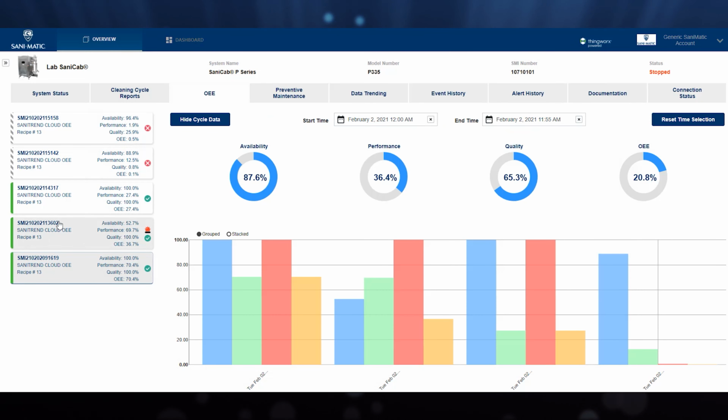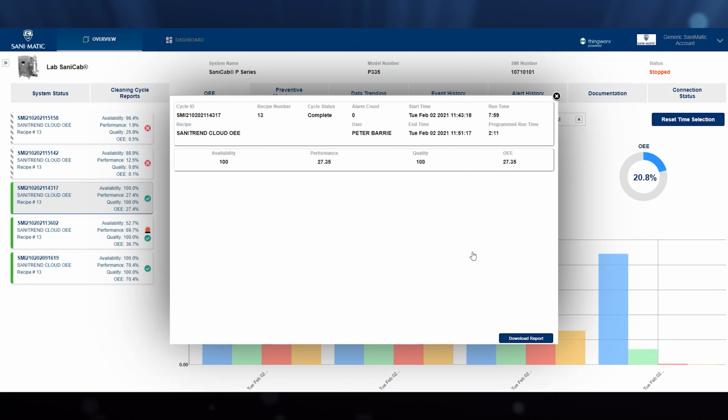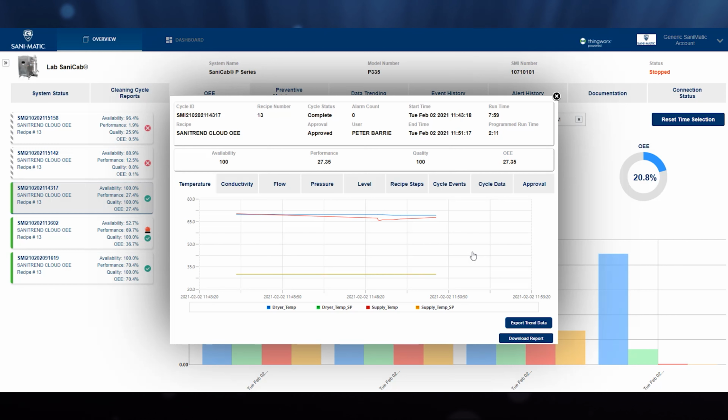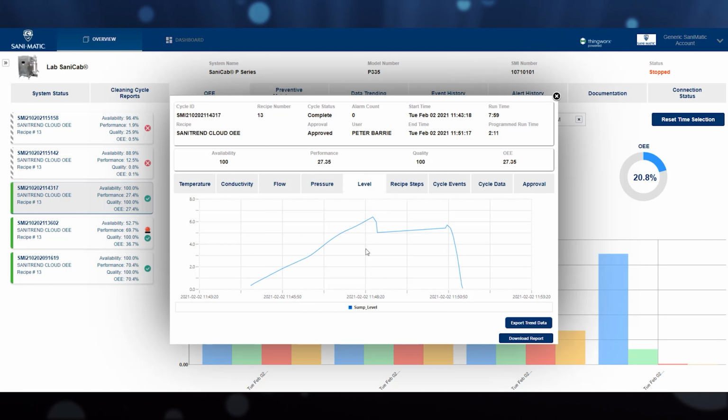And now I'll jump over to our recipe where we closed that water valve a little bit, right? So that water fill took a lot longer to fill up. And I can see that actually if I look at the level, right? Instead of a quick fill that we would have seen in our perfect recipe, I filled over 2, 3, 4 minutes or so. And this is common, right? If you don't have high enough water pressure, or something's going on with your water system, other utilities are using it, this can definitely happen. A normal 30-second fill can take 4 or 5 minutes, and if you compound this over multiple times in the overall wash cycle, obviously this can really extend your time.